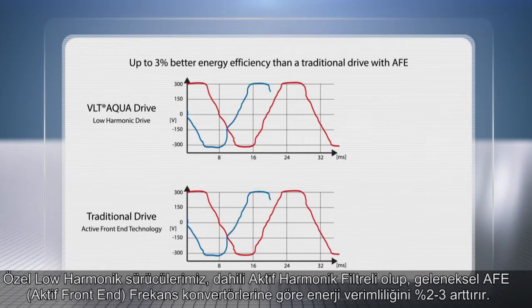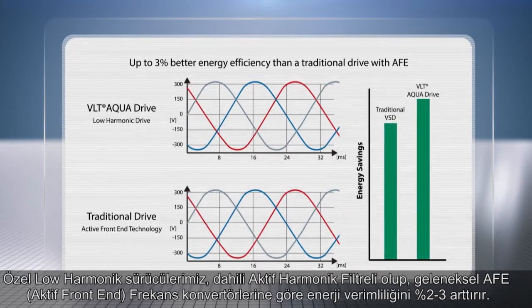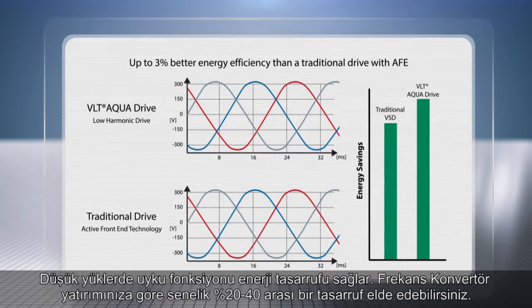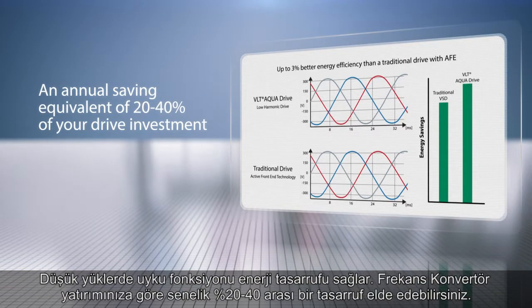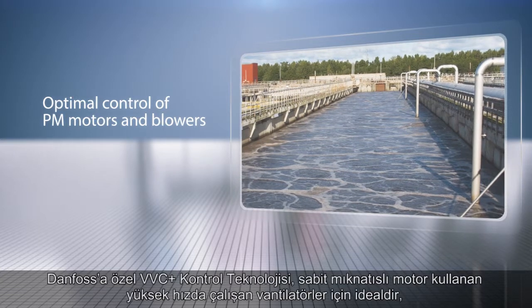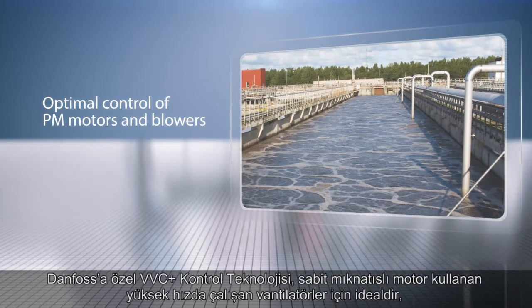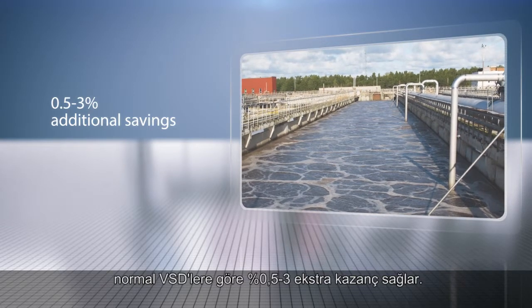Our unique low harmonic drive with integrated AHF filter delivers energy efficiency that is 2–3% better than a traditional VSD with active front-end technology. A sleep function at low load secures further energy savings — an annual saving equivalent of 20–40% of your drive investment. Unique Danfoss VVC Plus control technology is ideal for high-speed turbo blowers using PM motors, offering 0.5% to 3% additional savings compared to traditional VSDs.